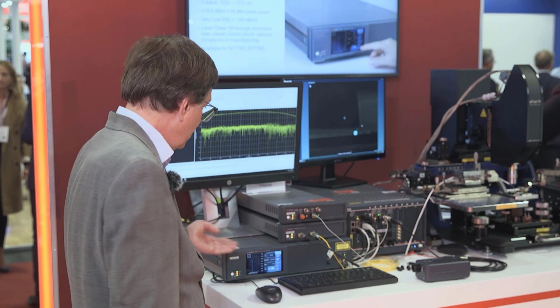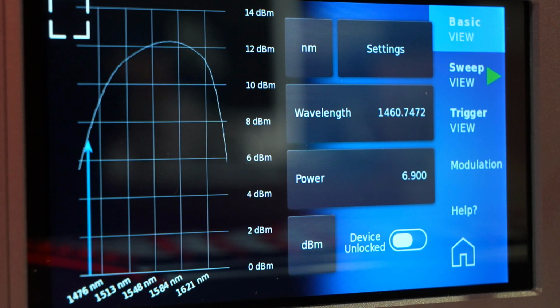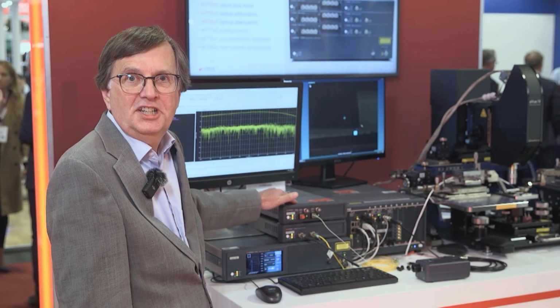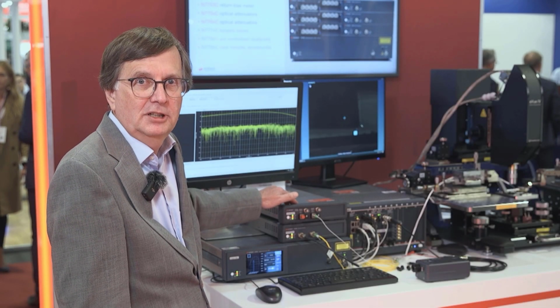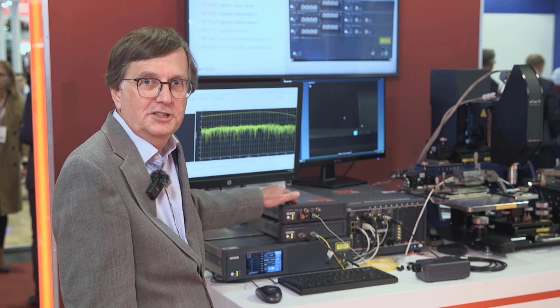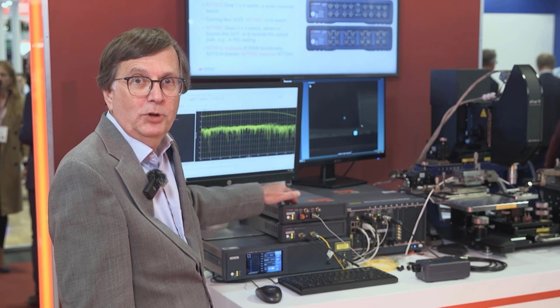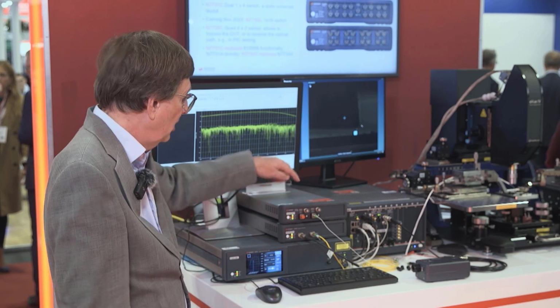The system combines one or more tunable lasers with a polarization controller and a variety of detectors. An optical power meter is used here for measuring devices with optical output like waveguides and modulators. Aligning the fiber probes is also supported with the analog output that provides a feedback for signal optimization, proportional linearly or for covering a wide dynamic range logarithmically to the optical power.